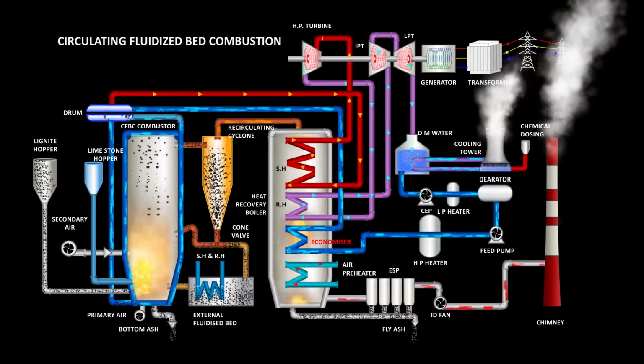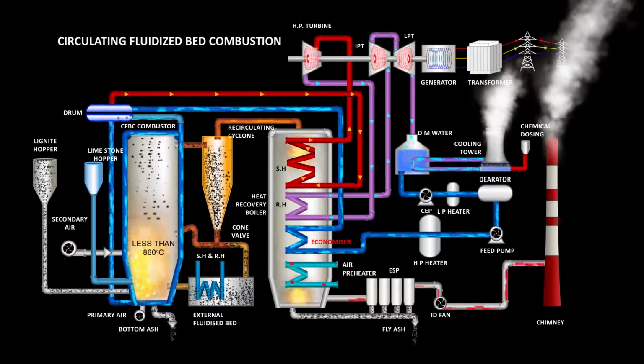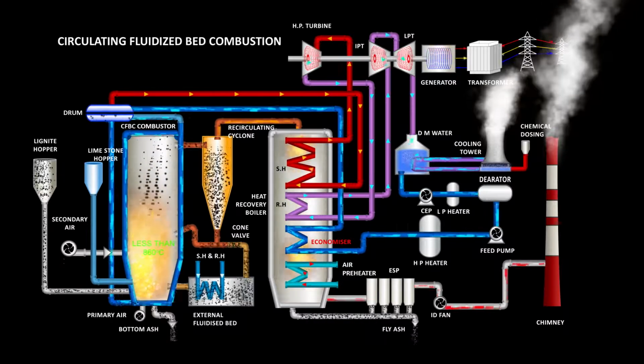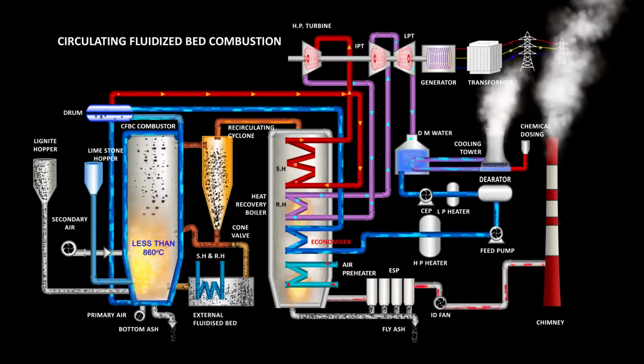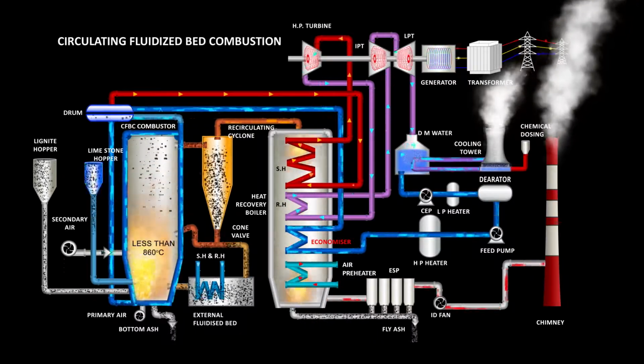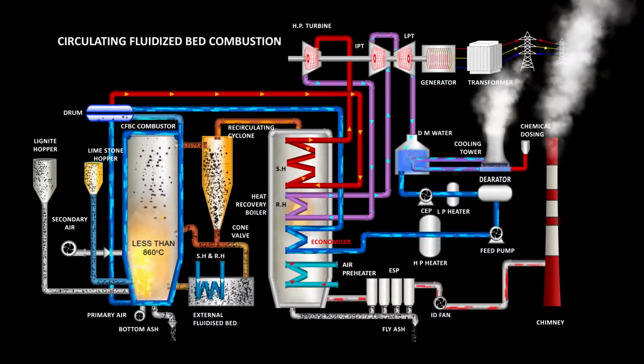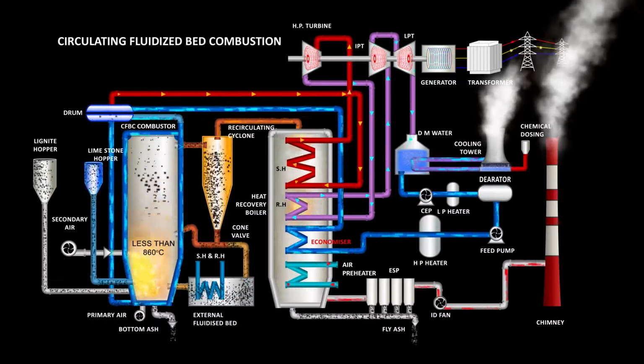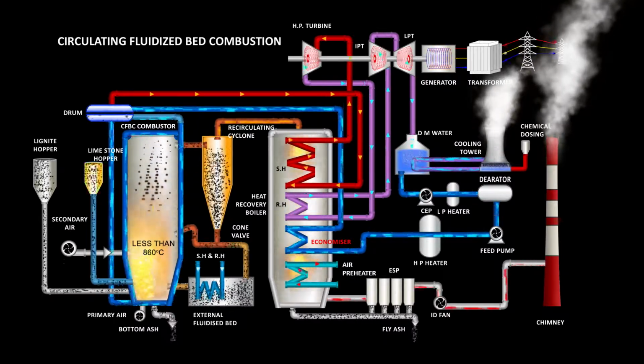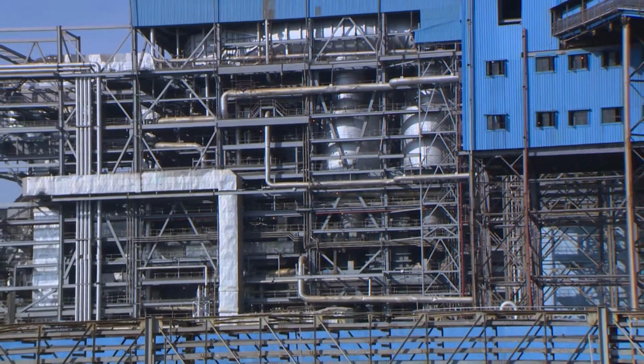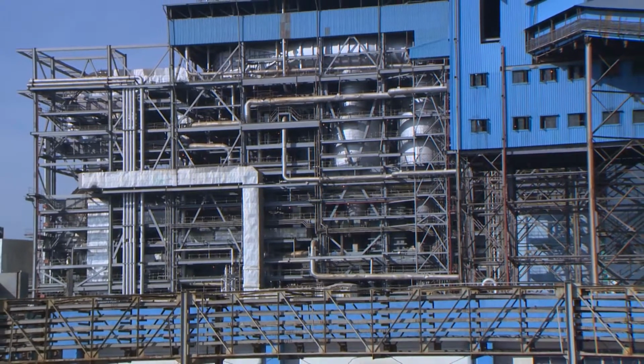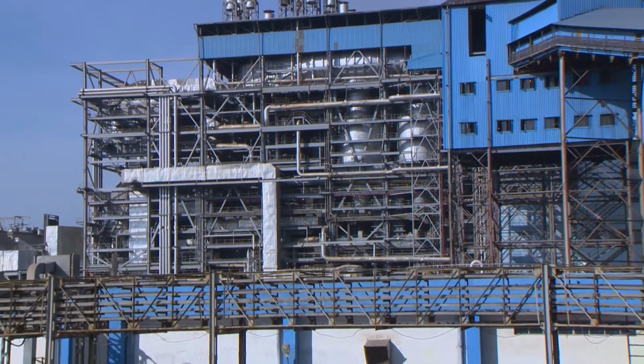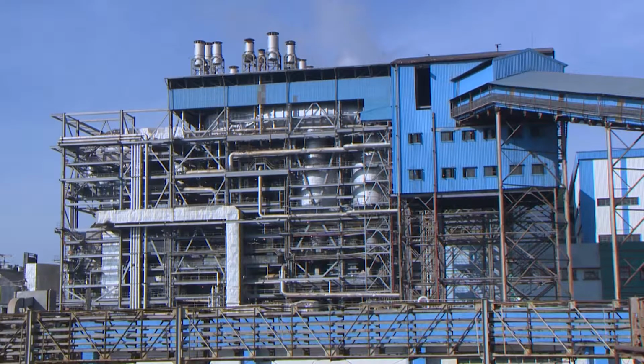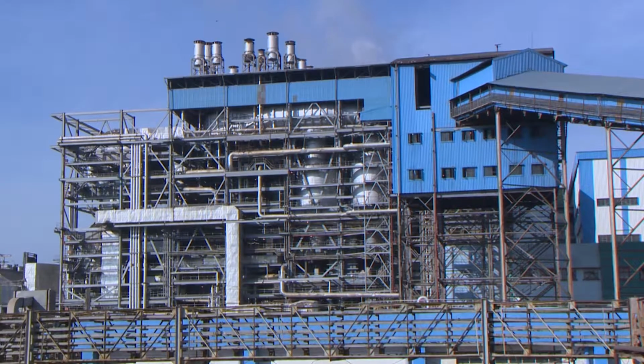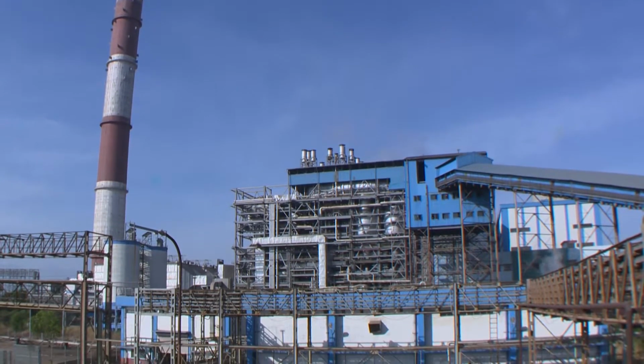Advantages of circulating fluidized bed combustion. The combustor temperature is maintained at less than 860 degrees Celsius, hence nitrogen oxide emission is minimized. Lime is added to the combustor for capturing sulfur oxide. Thus, sulfur oxide emission is also minimized. Hence, it is an eco-friendly boiler. The circulating fluidized bed combustion boilers at TPS-2 expansion are of new technology. This is the first of its kind in India for 250 megawatt units. These boilers are more efficient and eco-friendly.